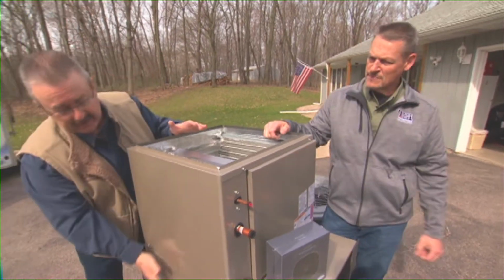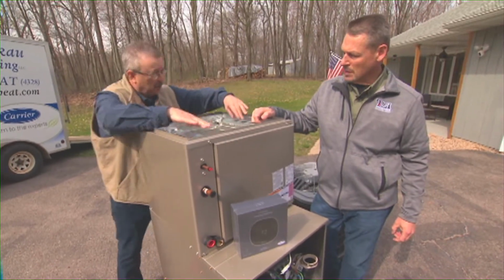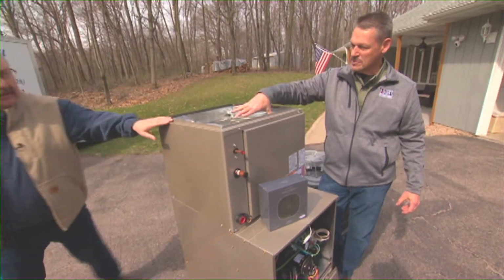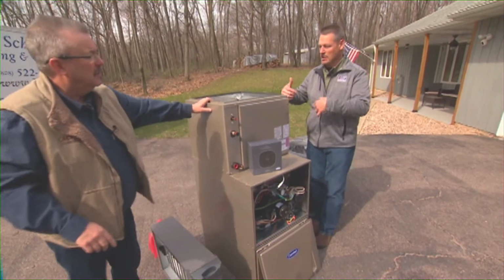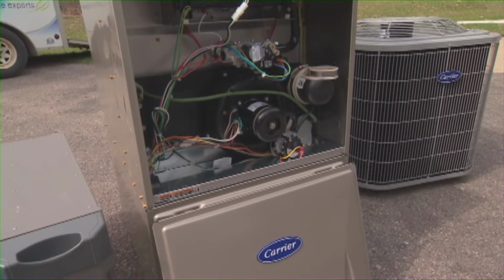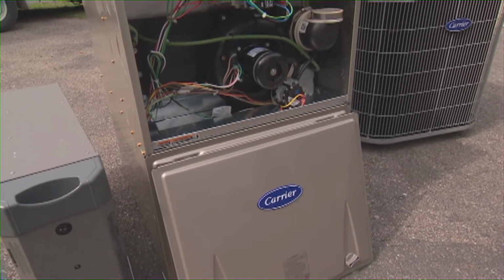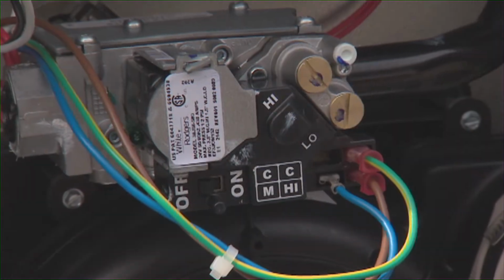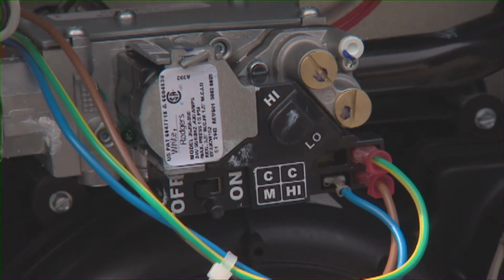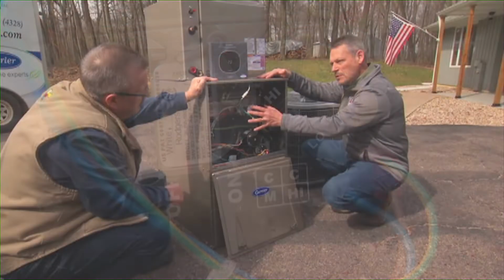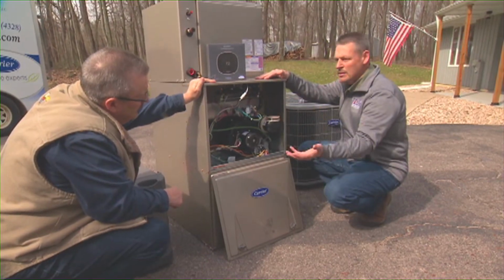And again, even though this is on top of the furnace, this is the air conditioning, the cooling side of the unit. Right, this is the portion that basically extracts the heat out of the home to cool the home down. Below this, we've got the furnace. In this case, this is a two-stage furnace going in. It has a two-stage gas valve, and that's important so we can better match the output of the furnace to the varying load the house experiences.